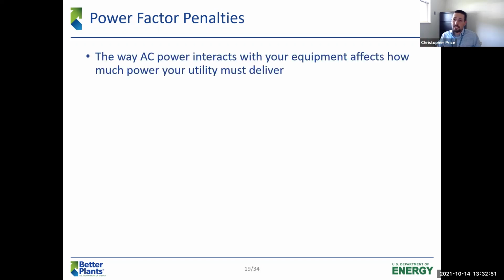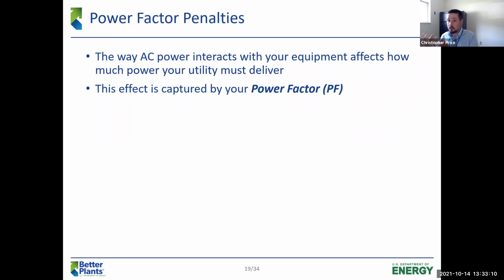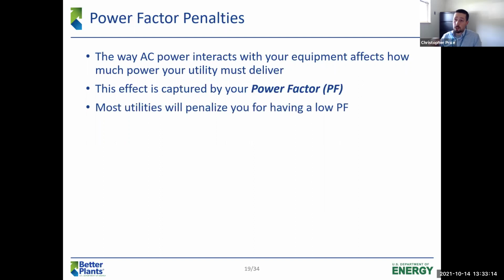The way that AC power interacts with the equipment in your facility affects how much power the utility has to deliver to your plant. How much extra power the utility has to deliver is captured by the power factor. Most utilities will penalize you for having a low power factor because it means they have to provide extra energy to your plant versus if you had a higher power factor.